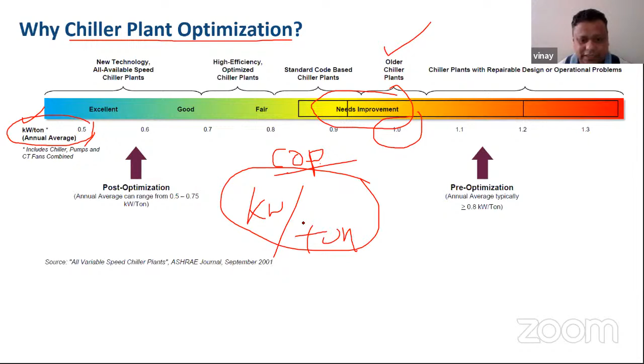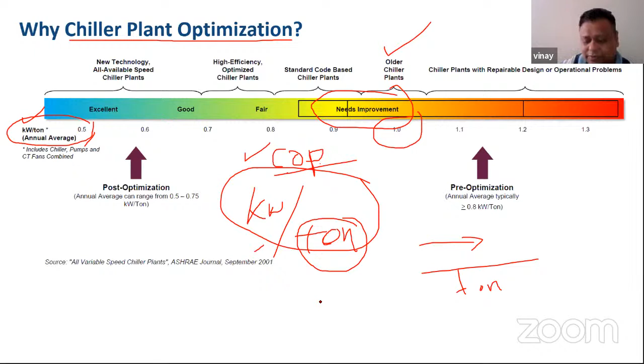How much electricity you are going to provide in relation to how many tons of refrigeration you are going to produce - that's the measure, that's why it's called kW per ton. COP is nothing but kW per ton, but in reverse. Most industries, maybe in the US, use COP as this kind of parameter.